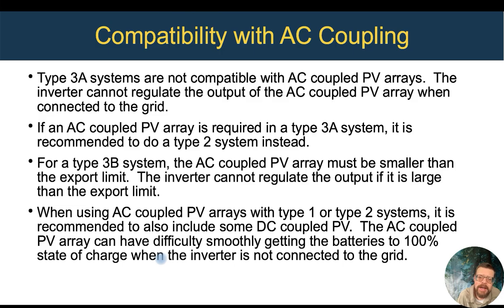Talk a little bit about details of AC coupling here and which systems work best with those. So as we discussed before, the Type 3A systems, zero export, are not compatible with AC coupled PV arrays. And that's because our inverter can't regulate the output of that AC coupled PV array and its separate inverter when it's also connected to the grid. So you do a Type 2 system where our inverter is not running in parallel with the grid, and then it can actually independently adjust the frequency to control that AC coupled PV array and turn it on and off. The Type 3B system, where we have limited output, the AC coupled PV array needs to be smaller than the export limit because it can't regulate down from that maximum if it's trying to produce more than the export limit.